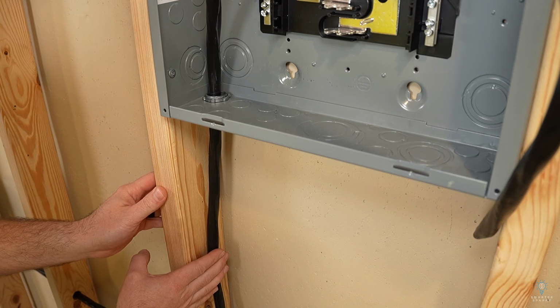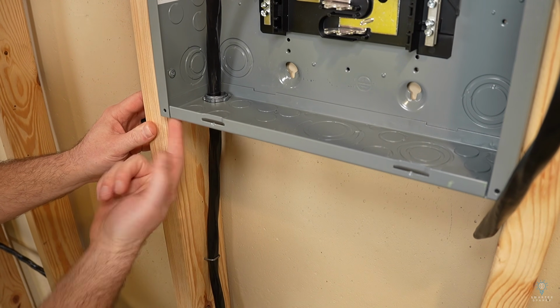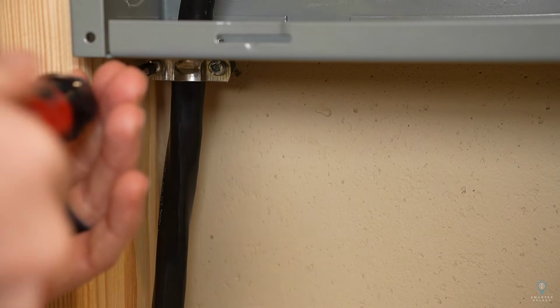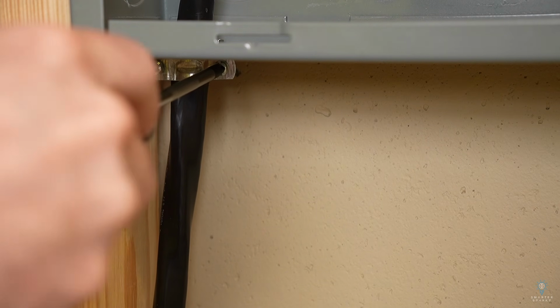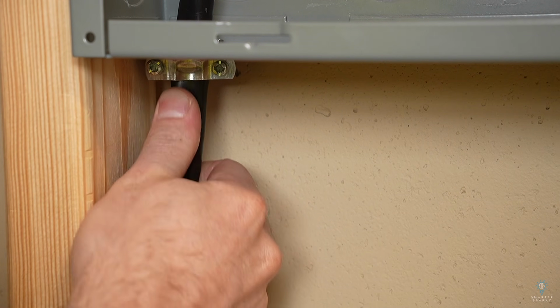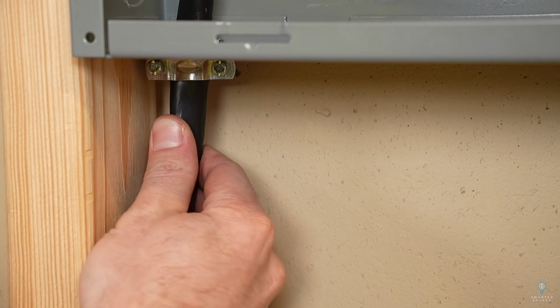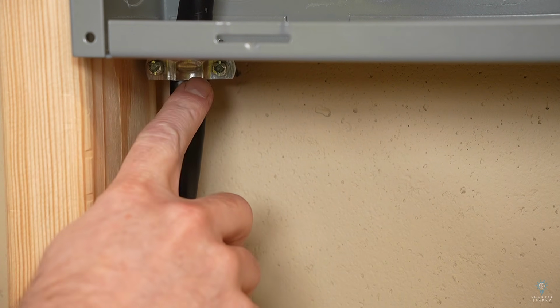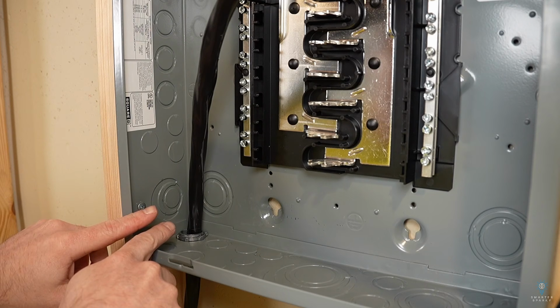So with our wire stapled and it entering the panel, we can go ahead and actually tighten down the screws on our connector. And we don't have to mash these down super tight. They just need to be snug enough that that wire is not gonna wanna back out. There we go. That wire is securely connected now to that connector. Now we can strip out the cable.